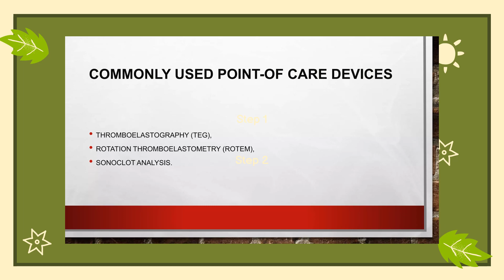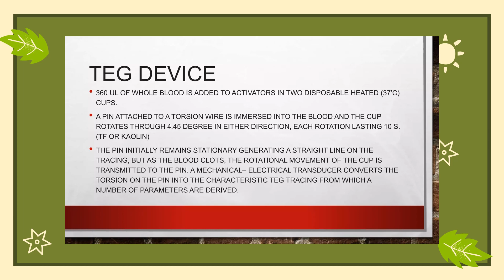A pin attached to a torsion wire is immersed into the blood and the cup rotates through 4.45° in either direction. The pin initially remains stationary, generating a straight line on the tracing, but as the blood clots, the rotational movement of the cup is transmitted to the pin. A mechanical electrical transducer converts the torsion on the pin into the characteristic TEG tracing, from which a number of parameters are derived.